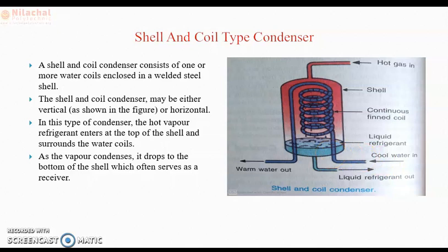Because of the counter flow, the temperature difference is uniform. For that reason, the counter flow is more efficient than the parallel flow. And the water coils are enclosed in a welded shell. Therefore, mechanical cleaning of this coil is not possible. So how to clean? The coils are cleaned with chemicals, and the shell and coil type condenser is used in units up to 50 tons capacity.